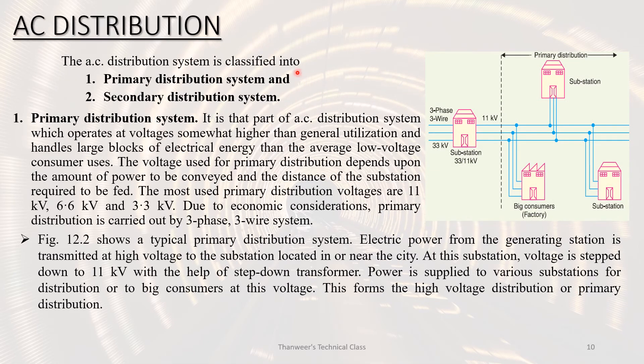For AC distribution, the system is classified into primary distribution and secondary distribution. In primary distribution, the voltage is higher — for example, a substation of 33 kV to 11 kV steps down to 11 kV or 6.6 kV for the primary distribution level. Distribution transformers then step down to secondary distribution voltage levels for consumer supply.